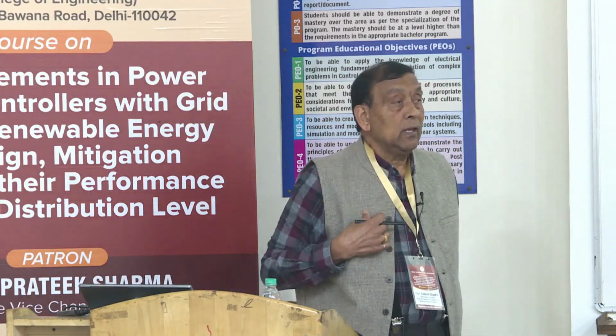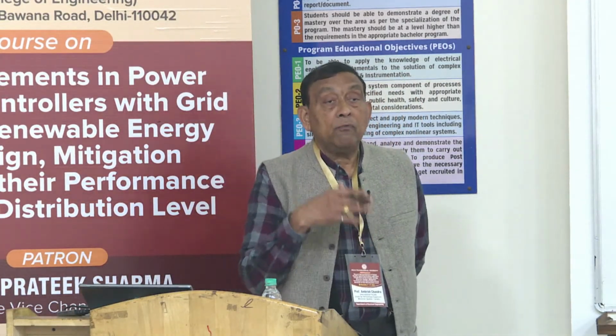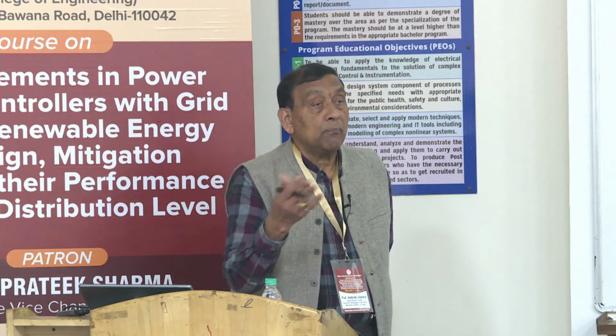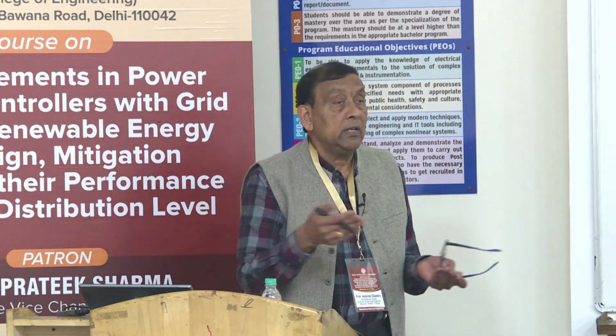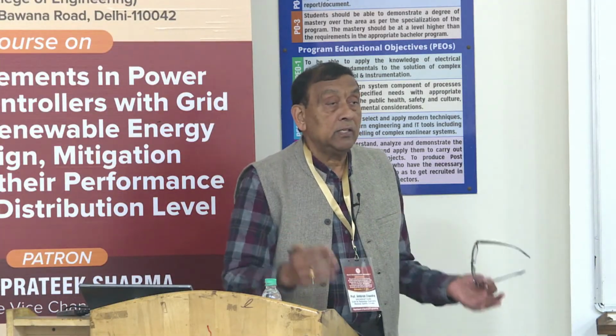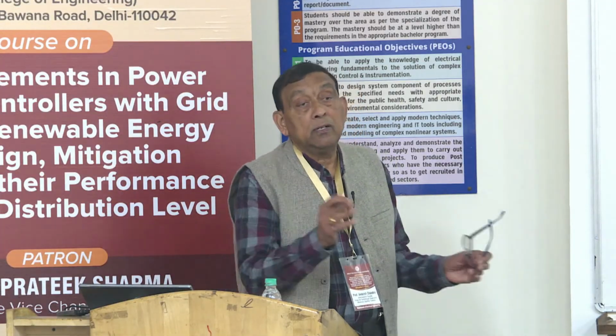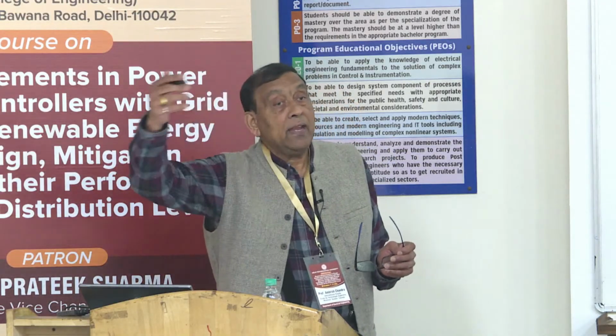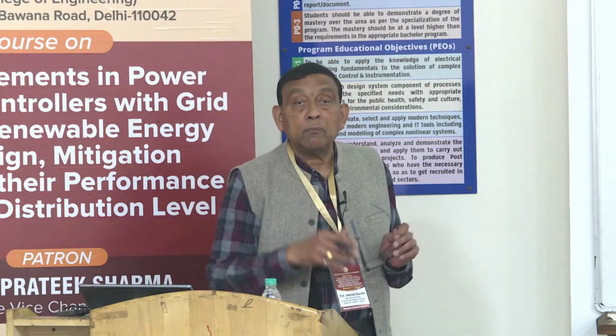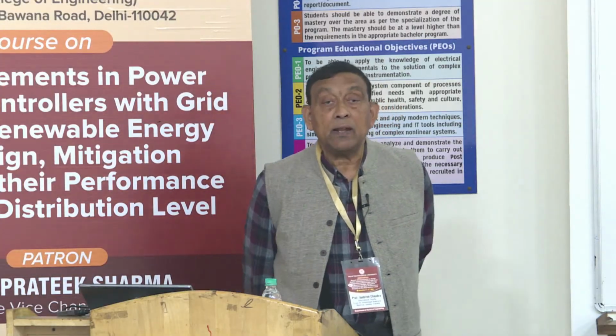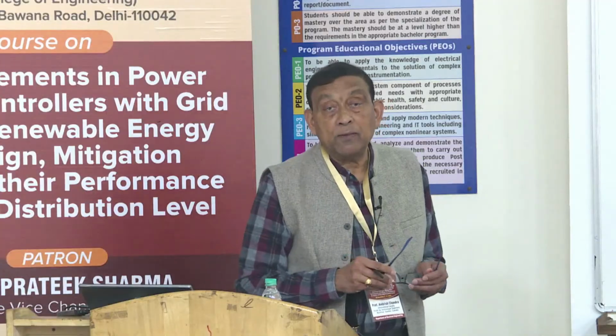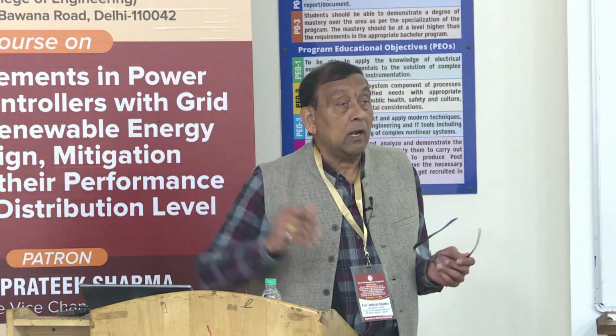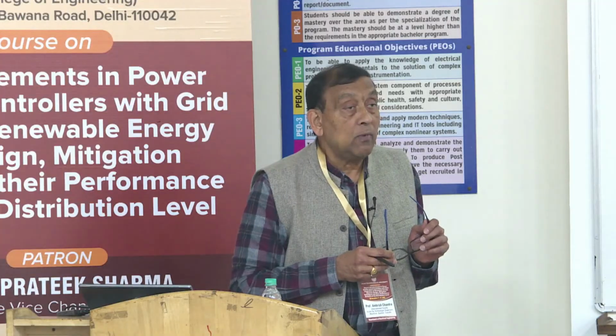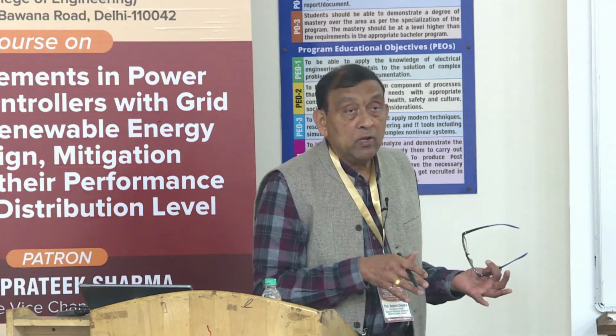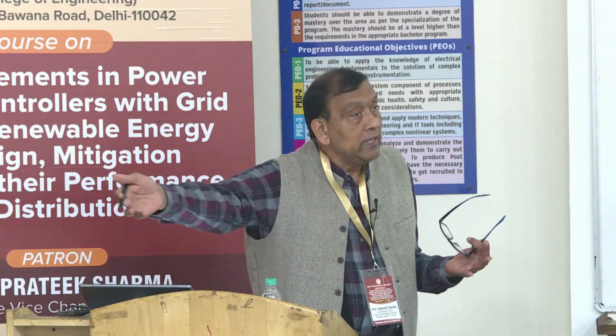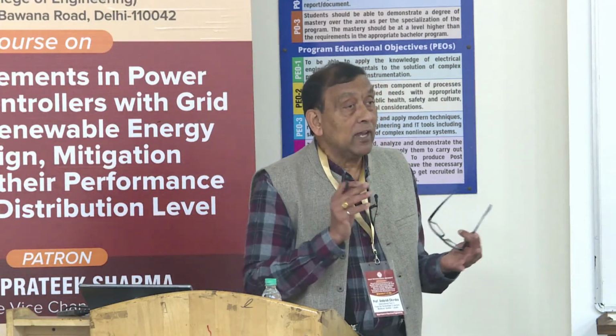Sometimes what we do, okay, there is a community which has some houses, and suppose it has a requirement of say 30 MVA of power, so you need a transformer. But then in future more residences will be added, so you may have more requirement. Perhaps instead of 30, you may need a 90 MVA transformer. So initially you don't want to invest in a 3-phase transformer for 90 MVA. It will be a very costly investment in the beginning.